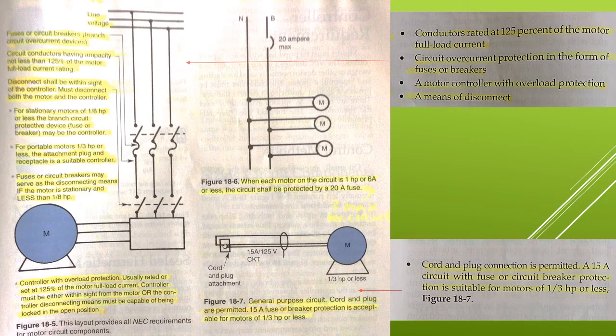General layout. Figure 18-5, on the left side of the screen, shows the general layout acceptable for a single motor branch circuit. This circuit must provide conductors rated at 125% of the motor full load current, top right of the screen, circuit overcurrent protection in the form of fuses or breakers, a motor controller with overload protection, and a means of disconnect.